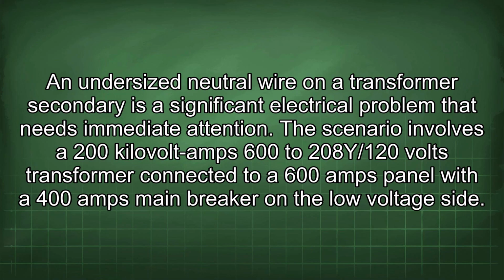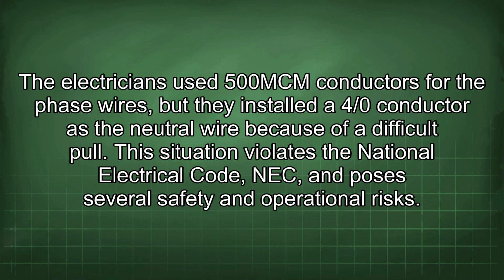An undersized neutral wire on a transformer secondary is a significant electrical problem that needs immediate attention. The scenario involves a 200 kVA 600 to 208Y/120 volt transformer connected to a 600 amp panel with a 400 amp main breaker on the low voltage side. The electricians used 500 MCM conductors for the phase wires, but they installed a 4/0 conductor as the neutral wire because of a difficult pull.